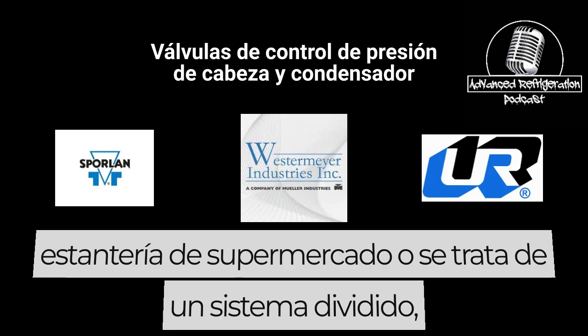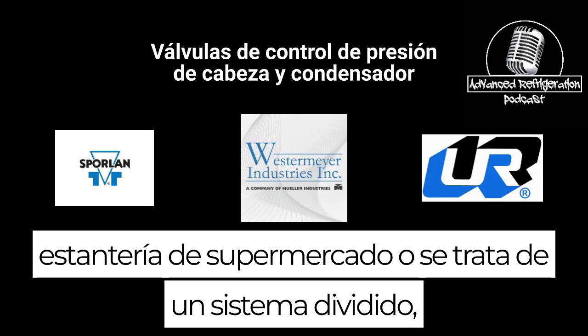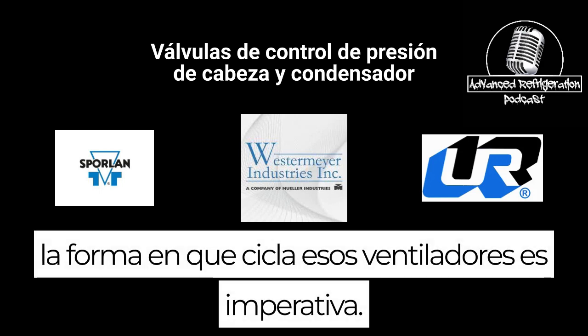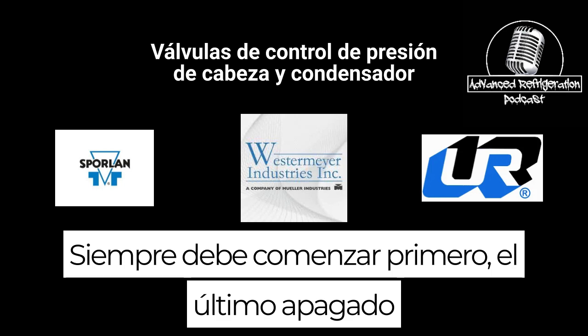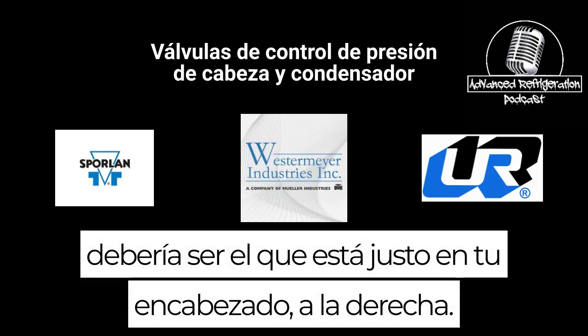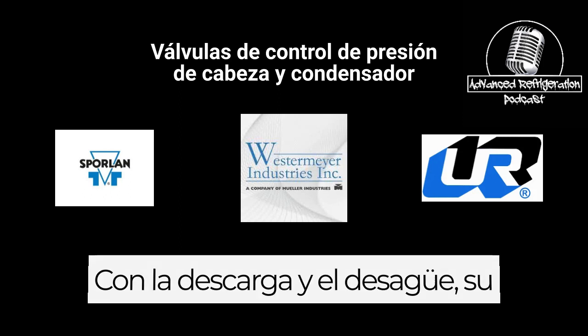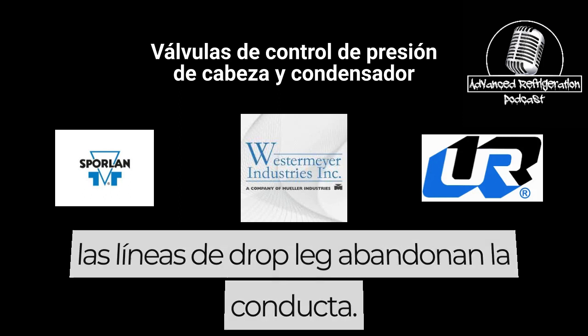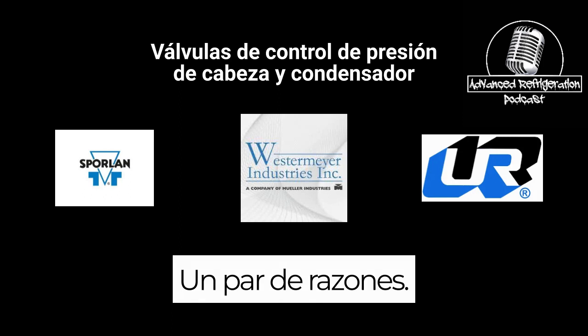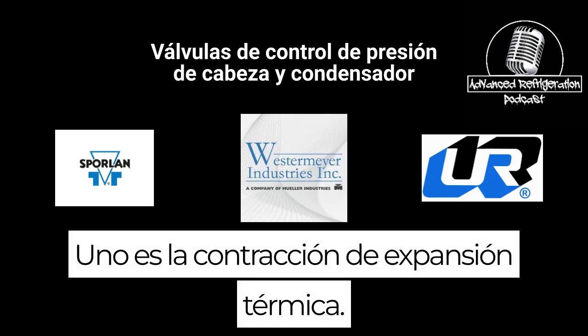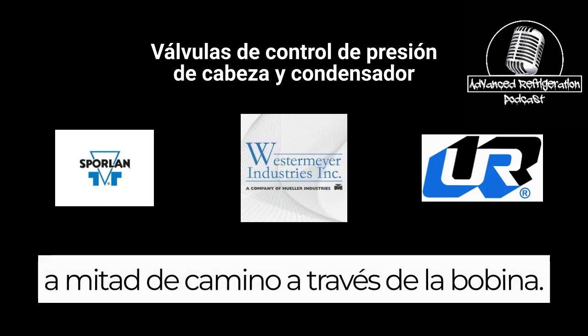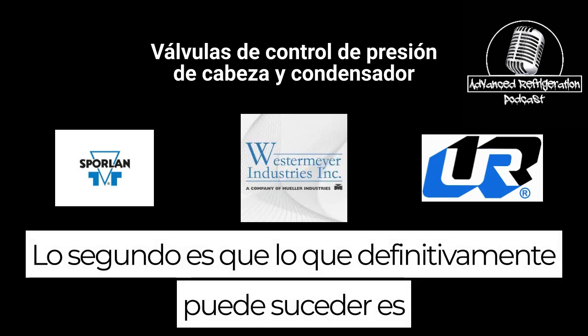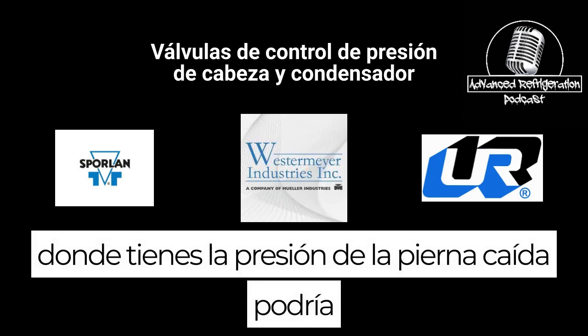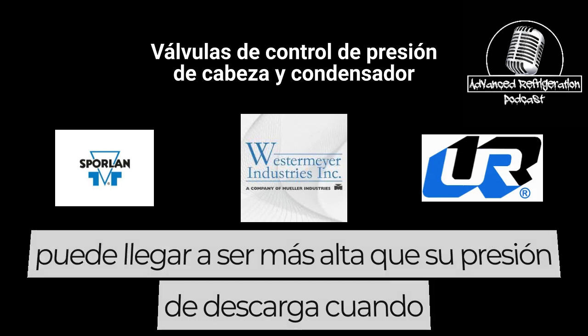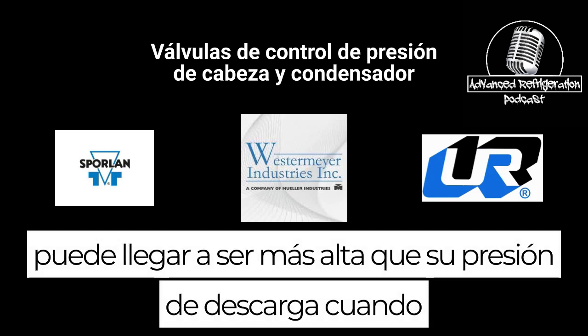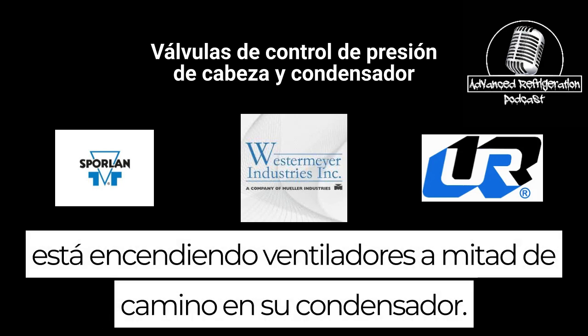Whether you're dealing with a supermarket rack or a split system, the way that you cycle those fans is imperative. You should always start with the first one on, and the last one off should be the one right at your header, right where the discharge and the drop leg lines leave the condenser. A couple reasons. One is thermal expansion and contraction. You don't want to be heating midway up through the coil. Second, which can definitely happen, is that the drop leg pressure could potentially get higher than your discharge pressure when you're turning fans on midway in your condenser.